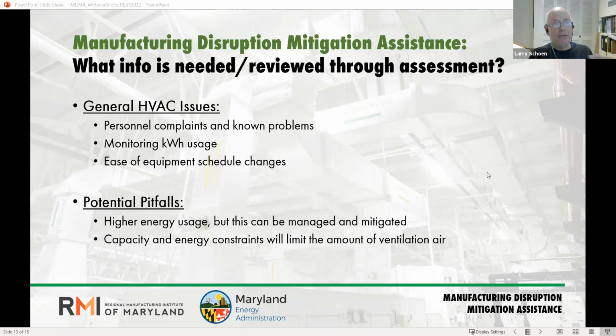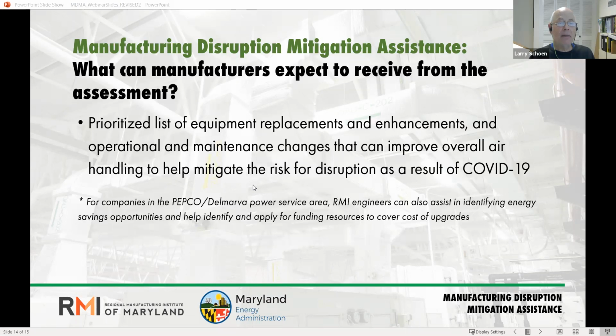So there sometimes is a balance under this pitfall list of certain actions, like pulling in more outdoor air and disabling demand-controlled ventilation, as I mentioned, can have an energy penalty, but those can be managed and mitigated. And the ERV and HRV, energy and heat recovery that we mentioned, is one of the ways to do that, to try to get both covered. And of course, we say more outdoor air, but systems have practical limitations, both for the amount of air that they can pull and the amount that they can condition that outdoor air. So these are all interventions that we can get a better handle on after doing an assessment of the facility. So next slide, Stacy. And I think we're back to you, Mike.